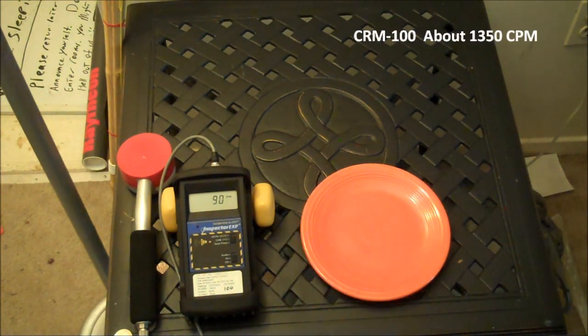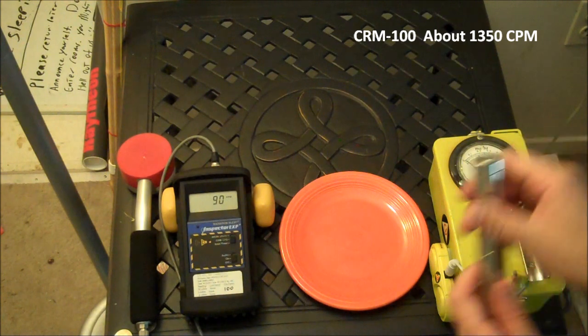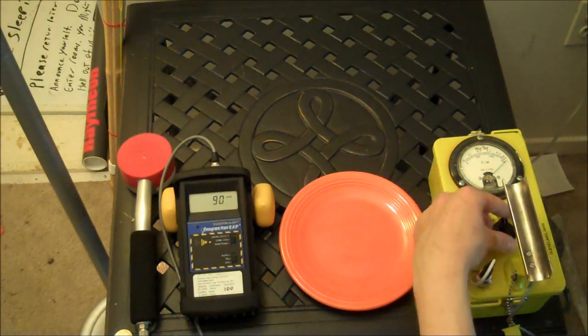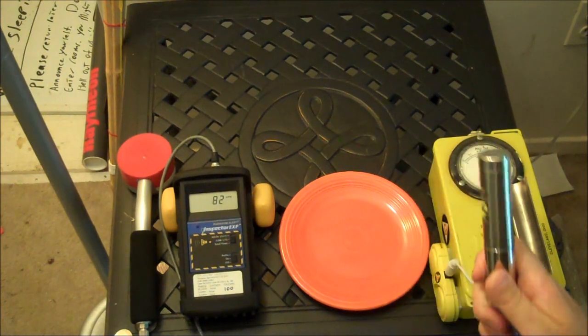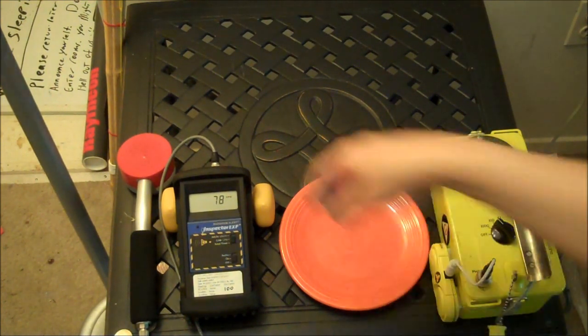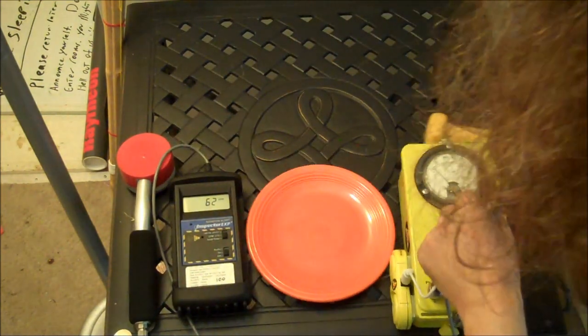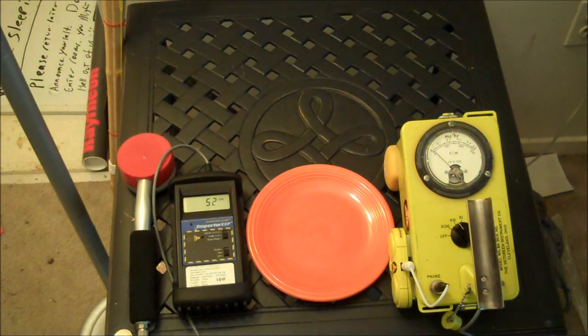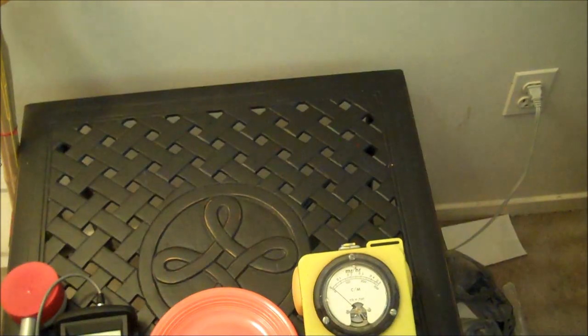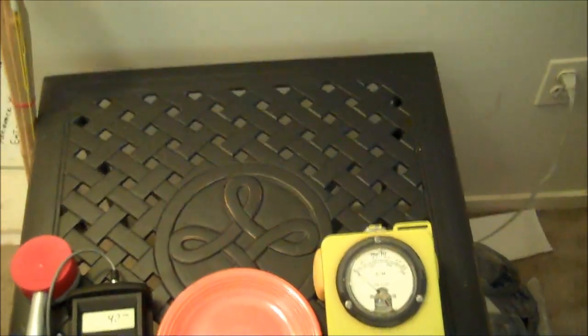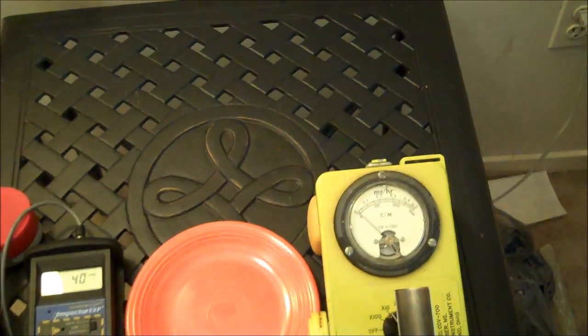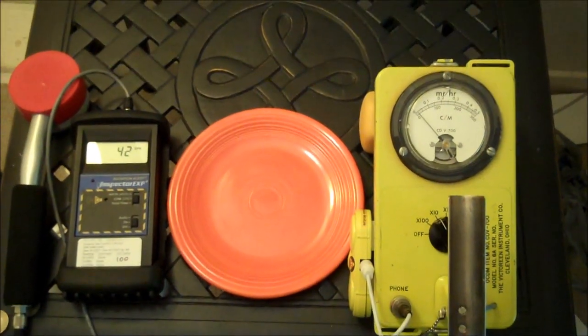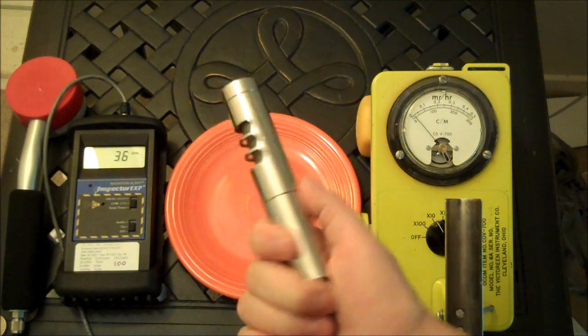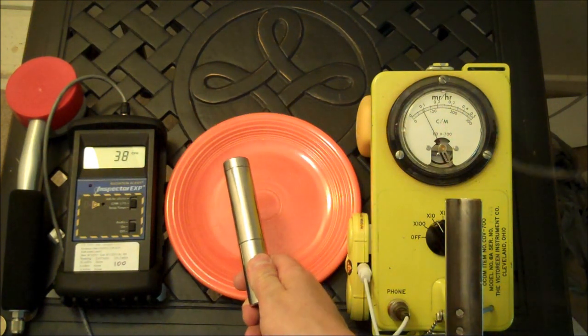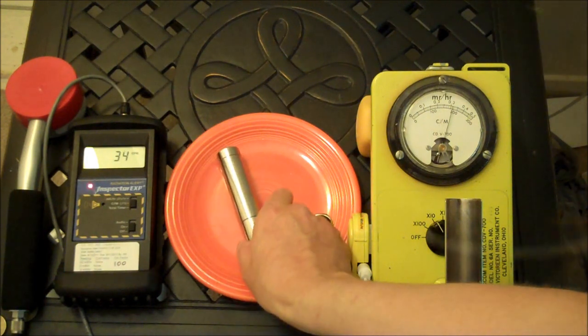Not too much. Now the CDV-700. Let's see how it does. Off scale. Go to times 10 mode. Let's see if you can see, by the way, the dial on that. Not too well. So let's prop it up just a bit, like that. And we'll lower the camera just a bit, so you can get a better view of this. Okay. So on the times 10 scale, with the beta shield open, contact, we're hard over, so we'll go to times 100.